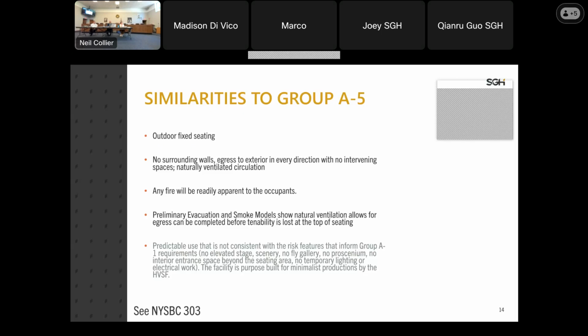We've looked at our evacuation and smoke models, which we have videos for you later. We found that in the context of the amount of time it takes for fire to be detected or an evacuation to start, we call those two times pre-movement time together, and then the time it takes for the actual evacuation with a factor of safety, everybody is gone out from under that shade structure before the effects of a fire, in this case heat, toxicity, or visibility come into play. If you've spent any time with smoke models, you know visibility is usually the limiting factor on tenability.